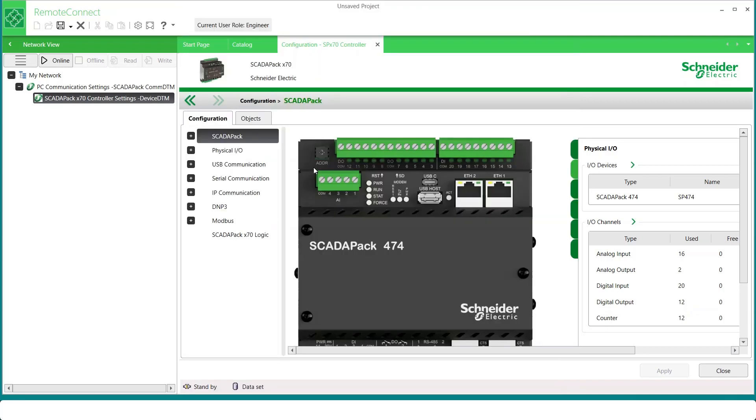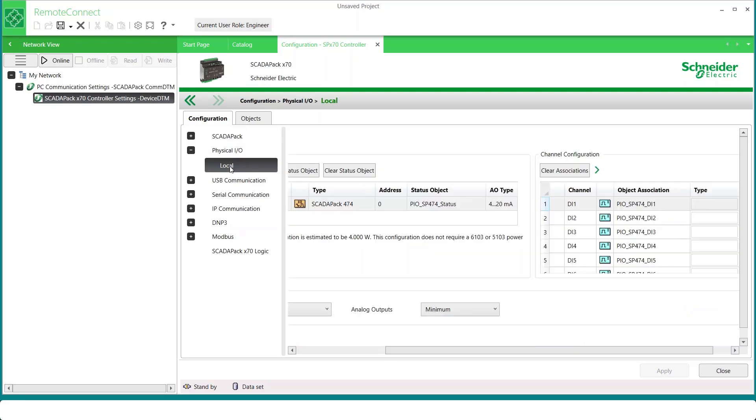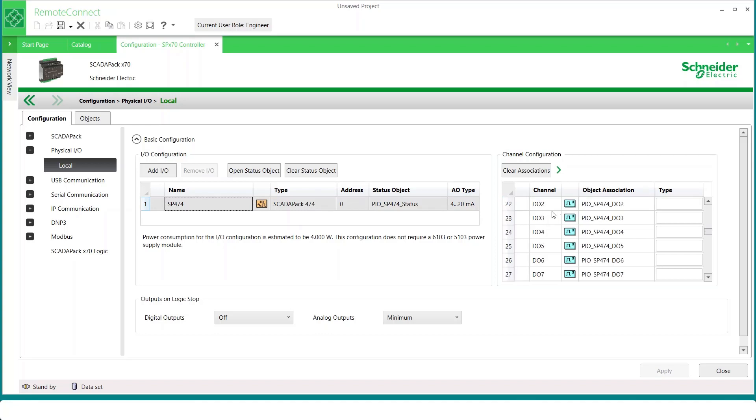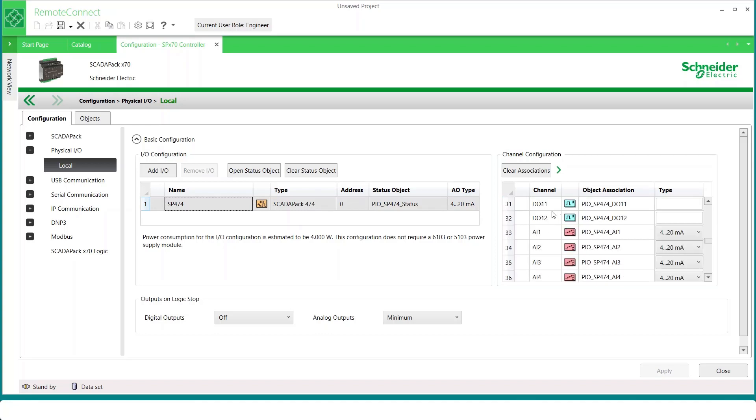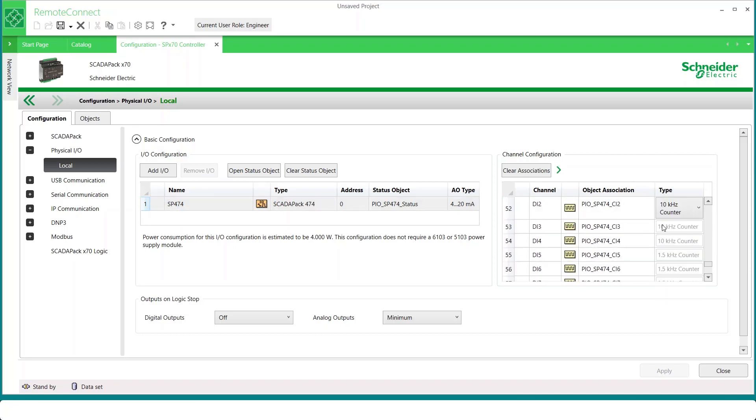To view, edit, and add physical I/O modules, here on the Configuration tab we can expand the Physical I/O section and select Local. Here we can see the default controller module, the SCADA Pack 474, and to the right is a list of all the default channels created. For analogs in, you can scroll down and change the input type. And for counters, you can change the counter type at this location as well.